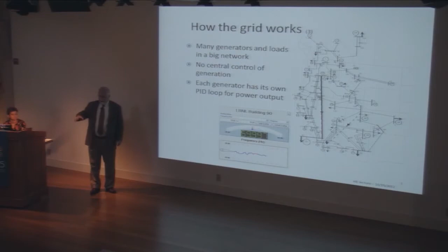All of the generators on this grid are spinning, and they're all carefully watching the local phase angle, the angle of their shaft with respect to the local voltage, adjusting their phase angles up and down to put out the correct amount of power. There is no central control of the generators on this huge grid; they all act independently by watching the grid locally. It's a wonderful system of cooperation, and it turns out to work and be fairly stable.